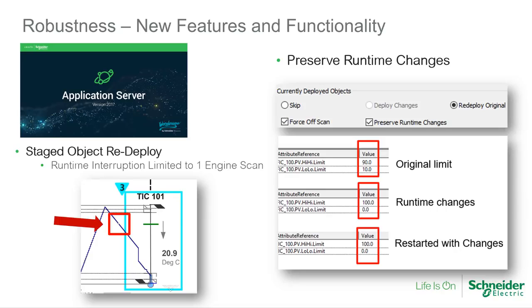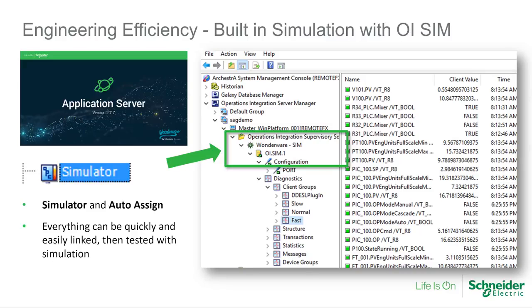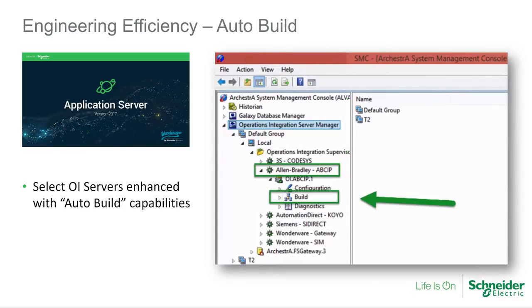Application Server has a new object redeployment mechanism, which reduces runtime interruptions to a single engine scan, providing a virtually seamless deployment of configuration changes at runtime. Complementing that is a new feature which allows users to optionally preserve changes made to important setpoints and other operator-settable values across deployment operations. The new simulation OI server provides application developers the opportunity to test their System Platform application using automatically bound simulated data. One of the exciting new engineering efficiency capabilities added to Wonderware System Platform 2017 is AutoBuild.